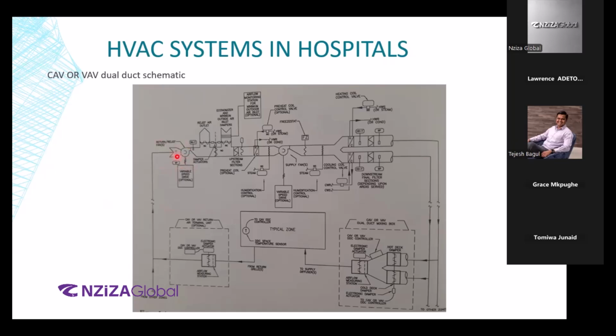we have the return air coming into the air handling unit, return air fan, relief air plenum, outside air introduction into the air handling unit, the pre-filter over here, heating hot coil, the steam humidification nozzles over here, supply air fan, freezestat, another set of steam humidification coil. And now this is where things get different. Over here you have a heating coil, okay, and the other part is the cooling coil. All right. We have the temperature sensors, we have the filters, and then we have the static pressure sensors.